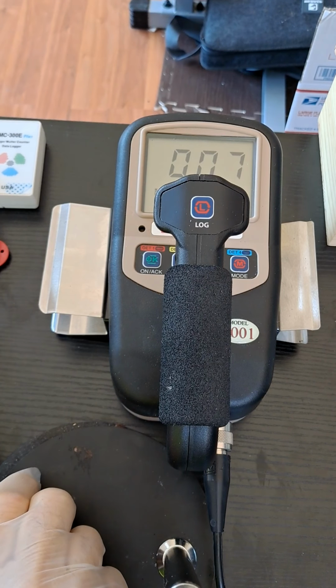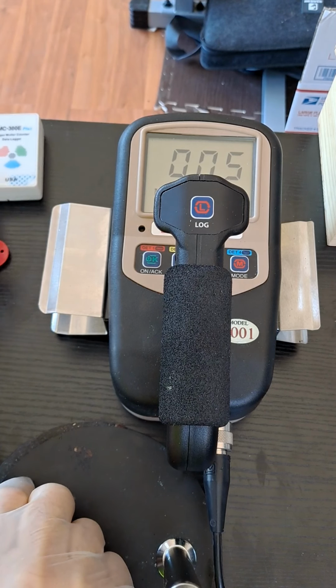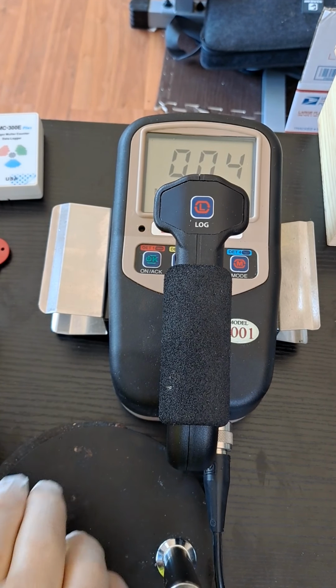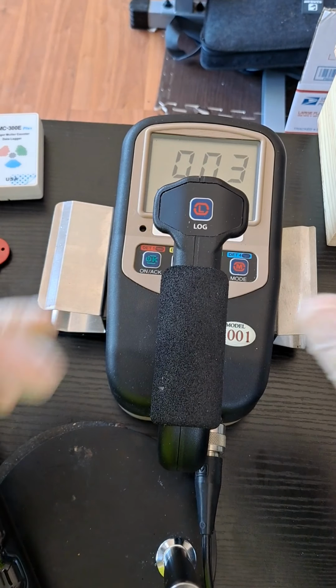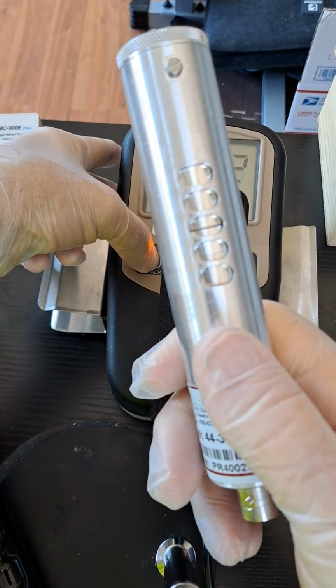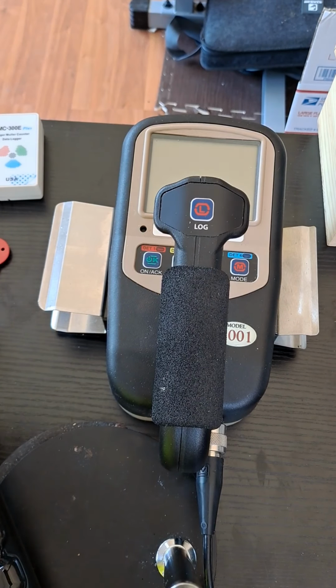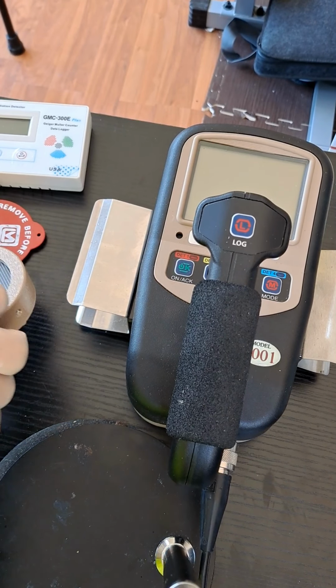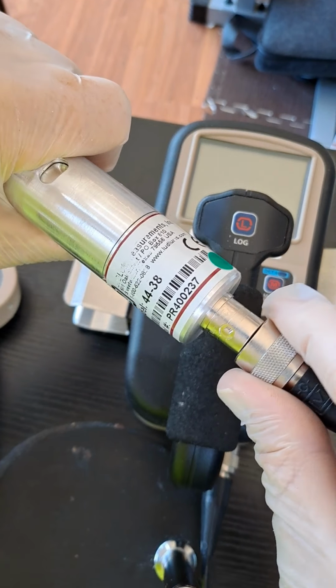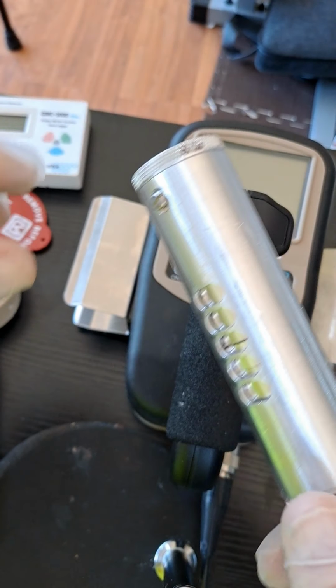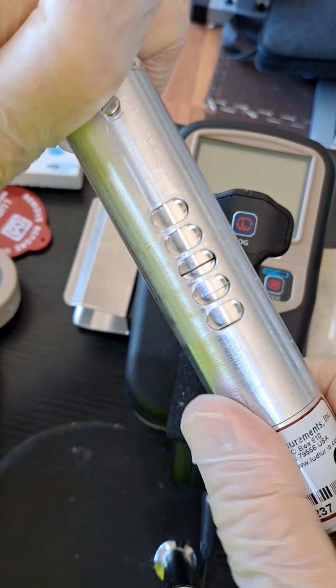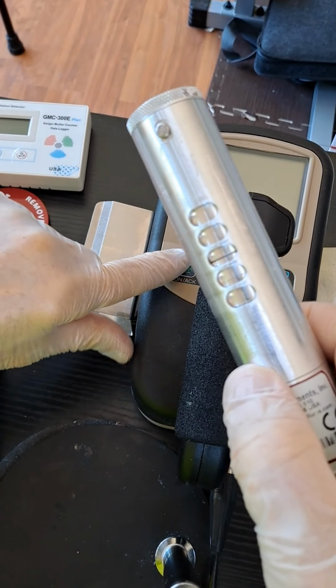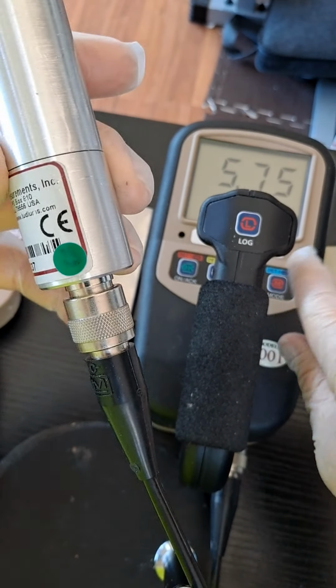Anyway, the final thing is there's a general probe. I first must turn this off. This is a beta gamma probe. Again, the same thing they use in nuclear power plants. And I'm turning off the machine. You then change out the probe, and you plug the new probe in. Now, to distinguish what type of radiation you have, it has an open window and a closed window. Open window is for beta gamma, closed is for gamma only. Then you turn the instrument back on. Notice the color is green.